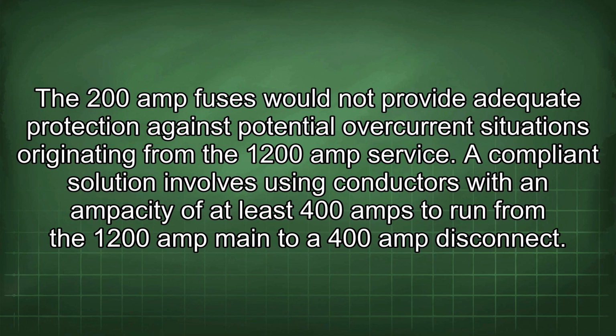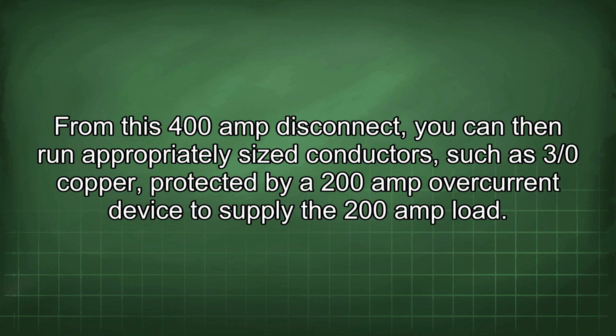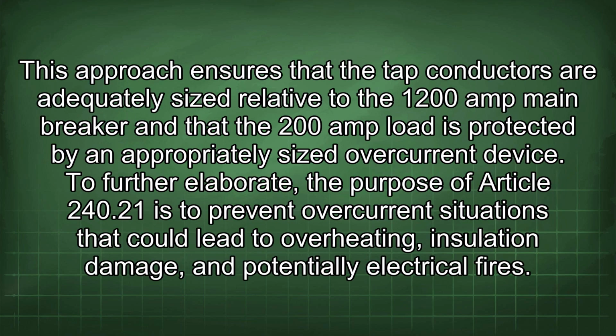A compliant solution involves using conductors with an ampacity of at least 400 amps to run from the 1200 amp main to a 400 amp disconnect. From this 400 amp disconnect, you can then run appropriately sized conductors such as 3/0 copper protected by a 200 amp overcurrent device to supply the 200 amp load. This approach ensures that the tap conductors are adequately sized relative to the 1200 amp main breaker and that the 200 amp load is protected by an appropriately sized overcurrent device.